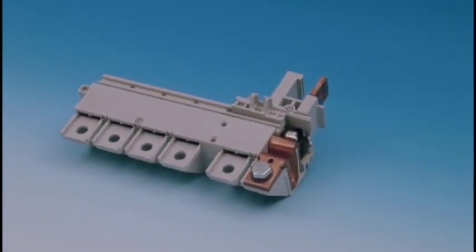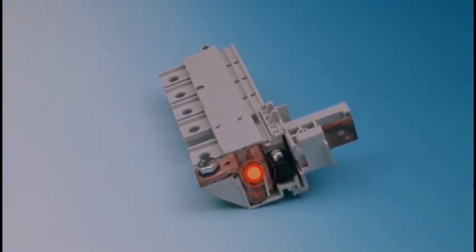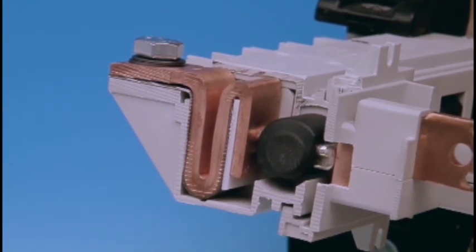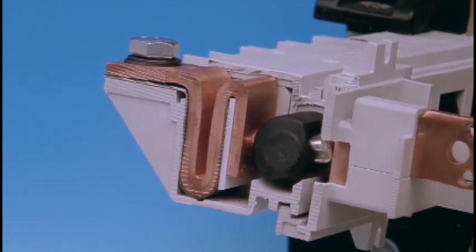There is no reciprocal movement of the parallel pressure contacts during a short circuit, because of their complete phase-to-phase encapsulation. Compared to finger contacts, there is no breaking of the magnetic field between the pressure contacts.